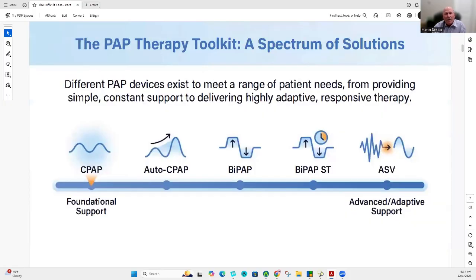Next slide. So what types of CPAPs are there? I'd say probably about 10, 15, 20 years ago we used to only use plain CPAP. You get a patient in, you put them on 8 centimeters of water. Pressures for CPAP are measured in centimeters of water. The average CPAP you're going to see is usually about 8 centimeters. When you start to get up past 12, you can blow the leaves off the driveway and your compliance rate really dips. So you have standard CPAP that was set at inspiratory 8, expiratory 8. Now we have the auto unit, which is going to fluctuate with what you need. So if you need a little, the machine will go down to say 6 or 4 or 5. If you need more, it'll go up to 10 or 12. It just depends on what you're requiring.